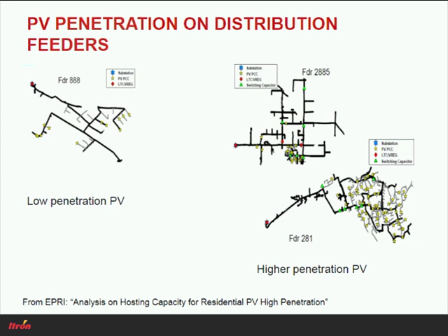When we talk about higher penetration, we're really talking about where PV may constitute up to 50% or more. In many utilities now, we're beginning to see, in the case of Sacramento Municipal Utility District, PV capacity which exceeds 50% of the peak demand of the feeders. And in some cases, we know from studies by NREL and EPRI that utilities face much higher penetration levels going in the future. In Hawaii, I know that they're talking about 80% penetration in some cases. So what does this really mean when you start getting high penetration PV?